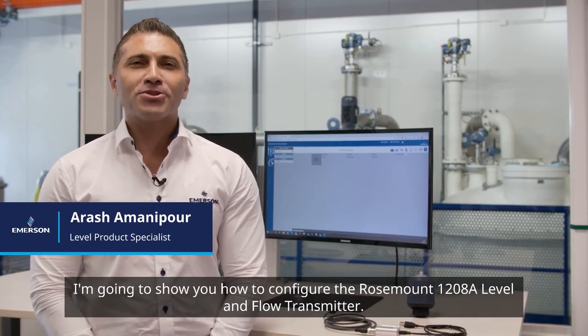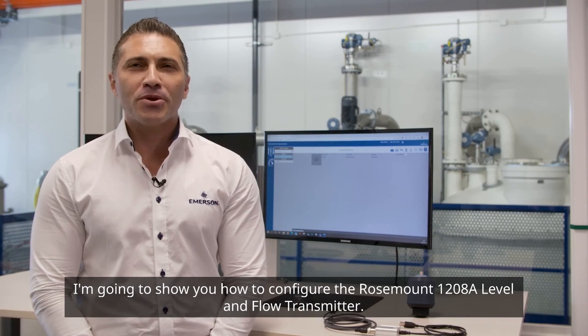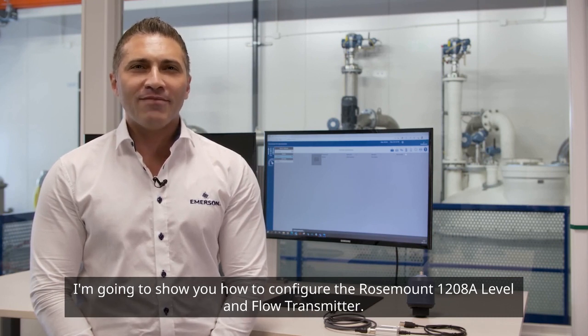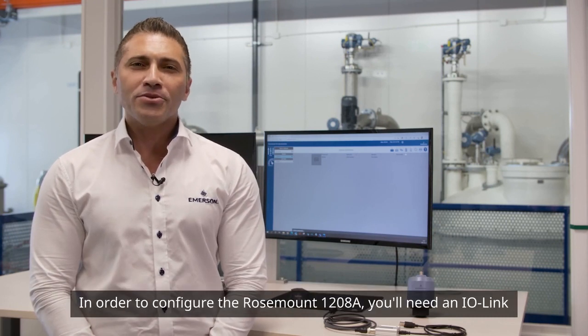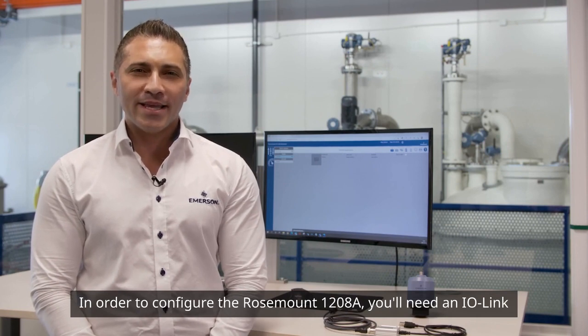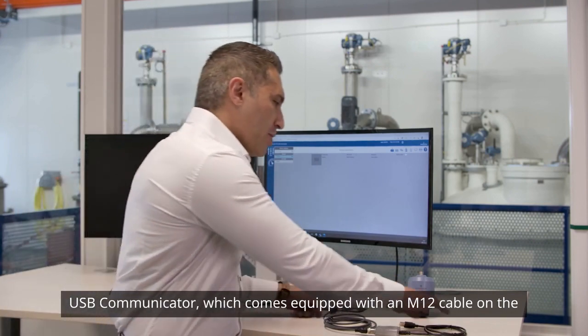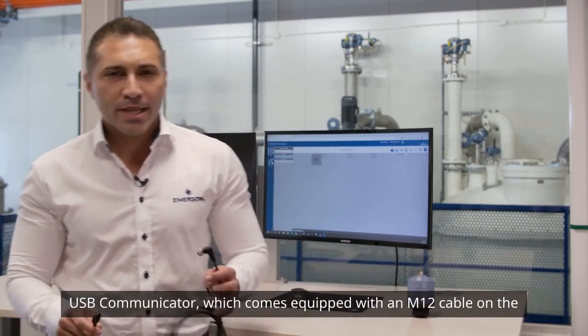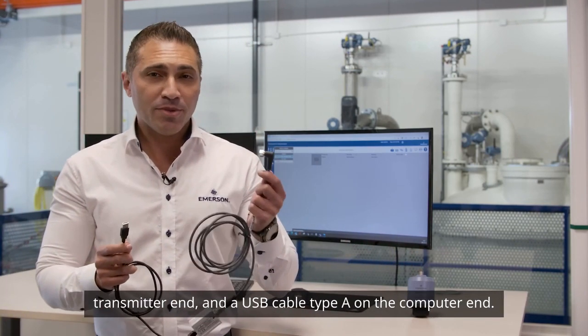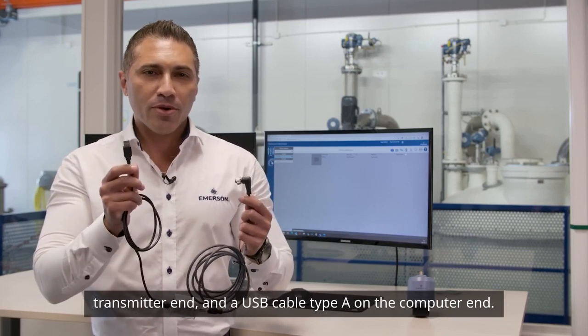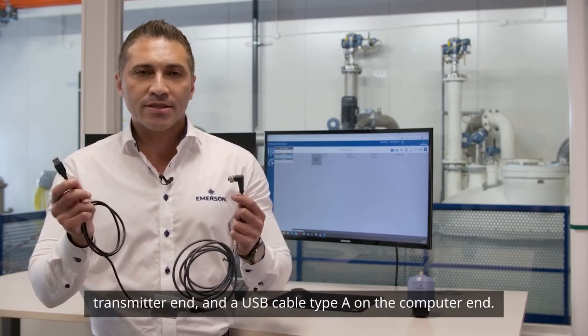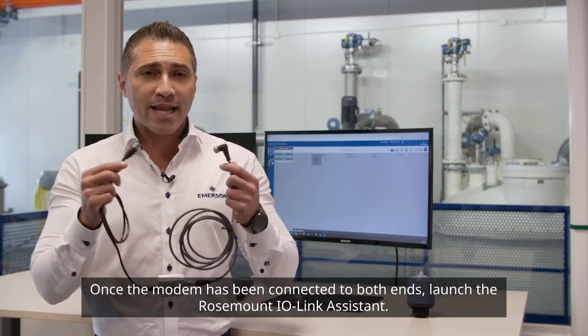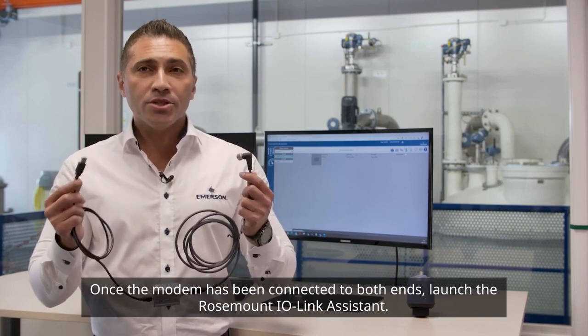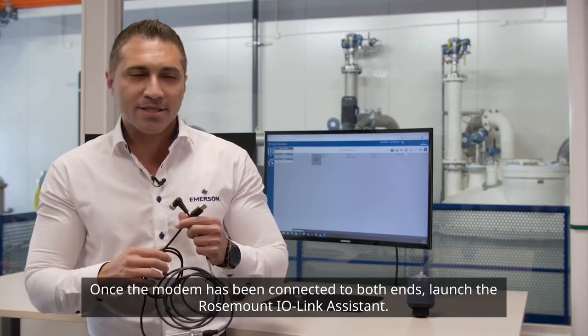Today, I'm going to show you how to configure the Rosemount 1208A level and flow transmitter. In order to configure the Rosemount 1208A, you'll need an IO-Link USB communicator, which comes equipped with an M12 cable on the transmitter end and a USB cable type A on the computer end. Once the modem has been connected to both ends, launch the Rosemount IO-Link Assistant.